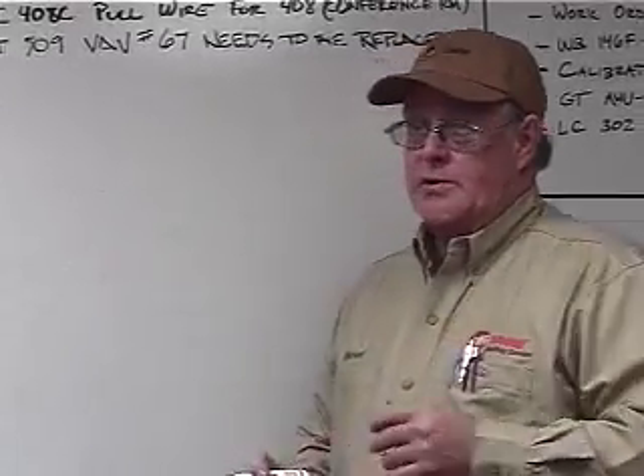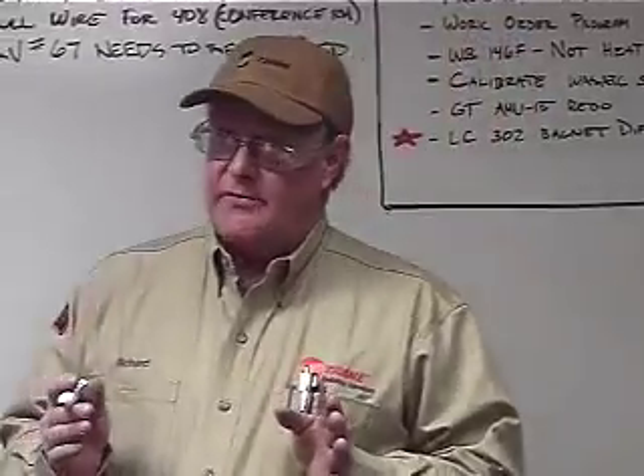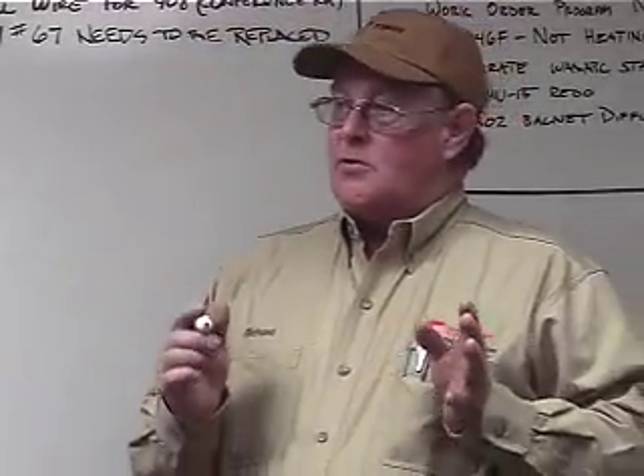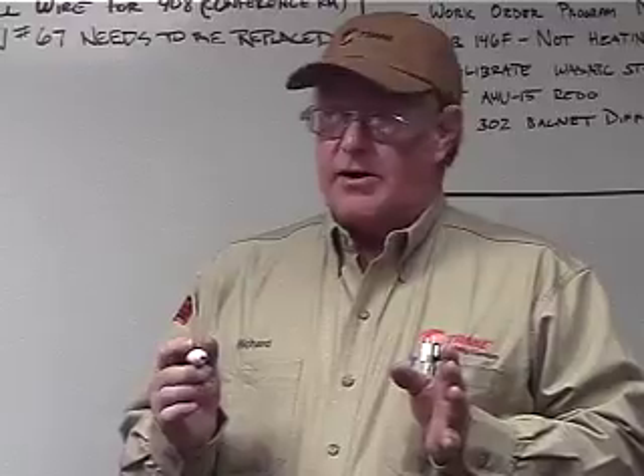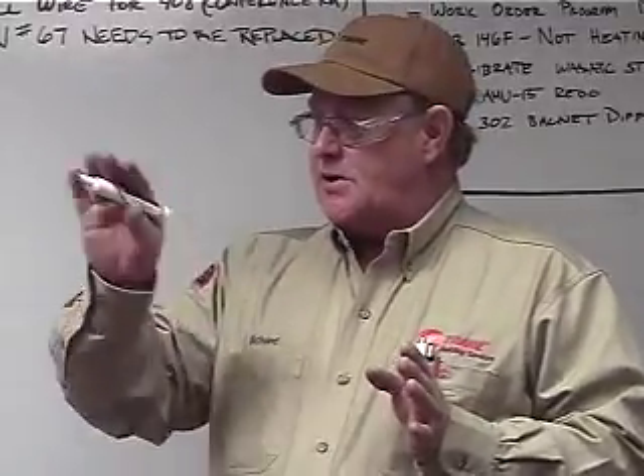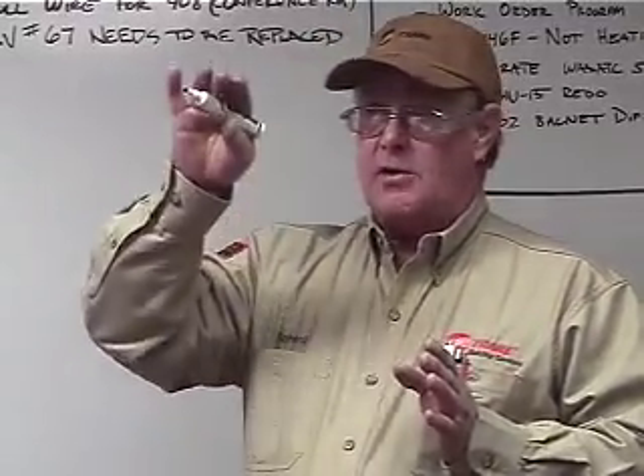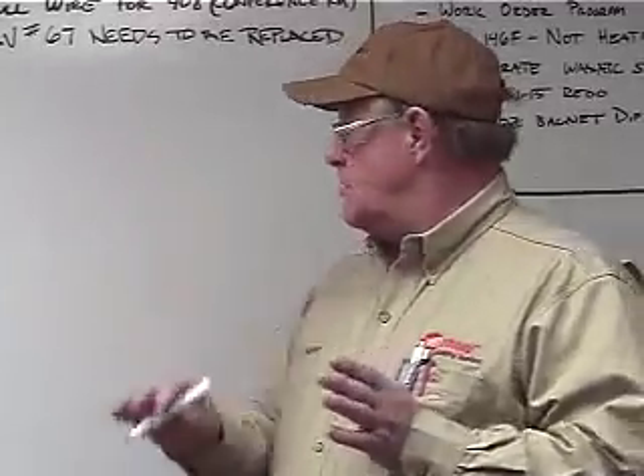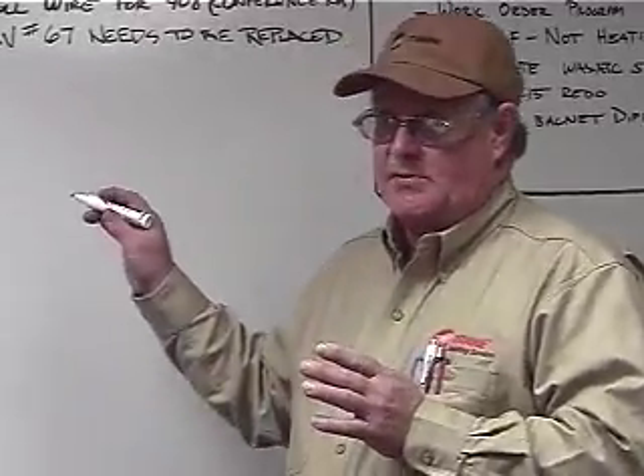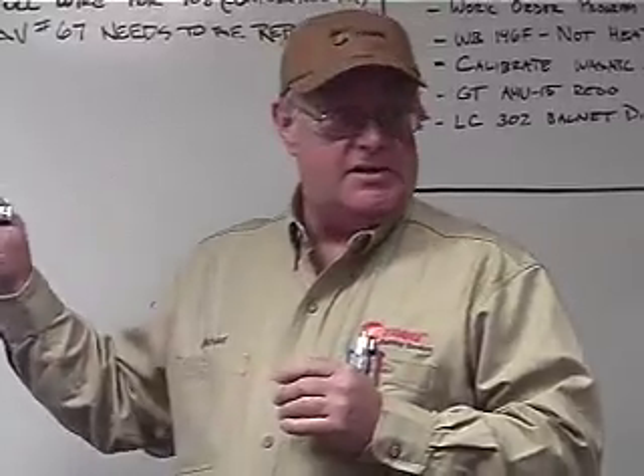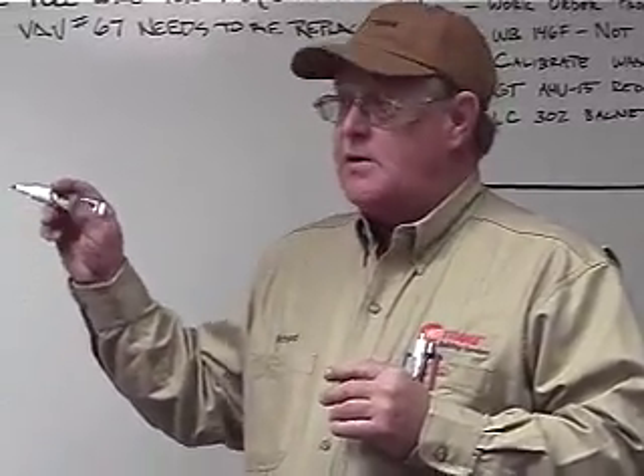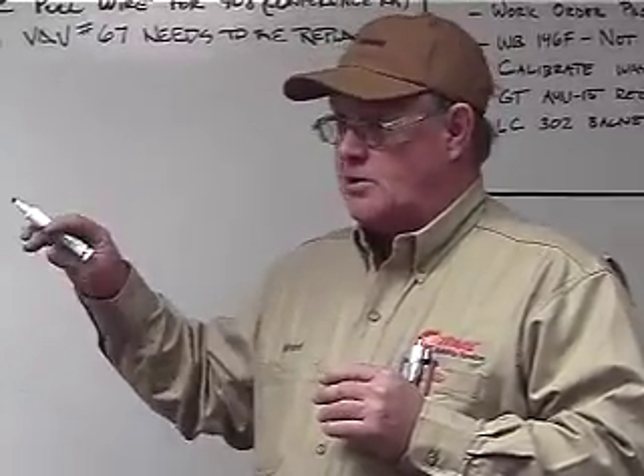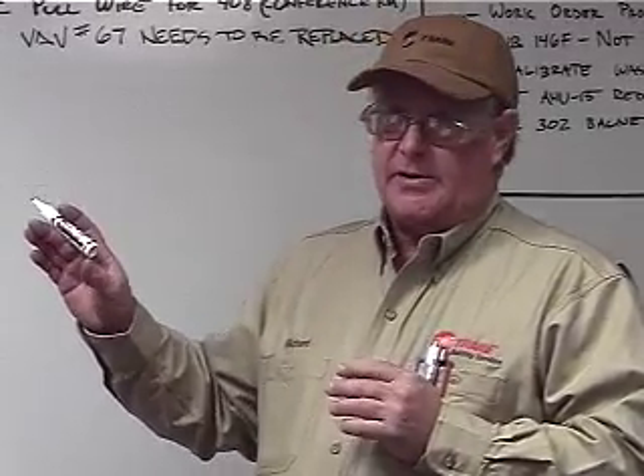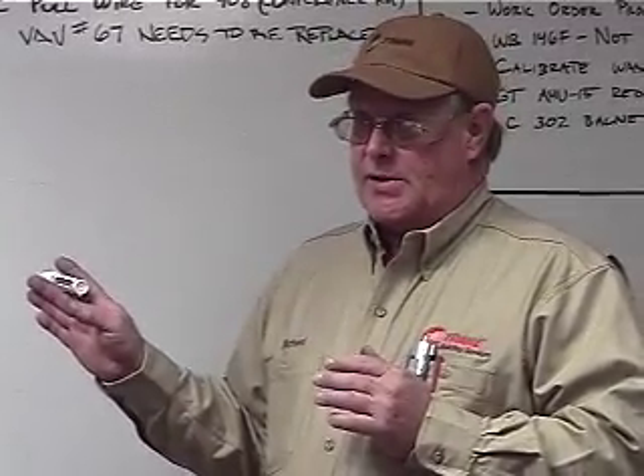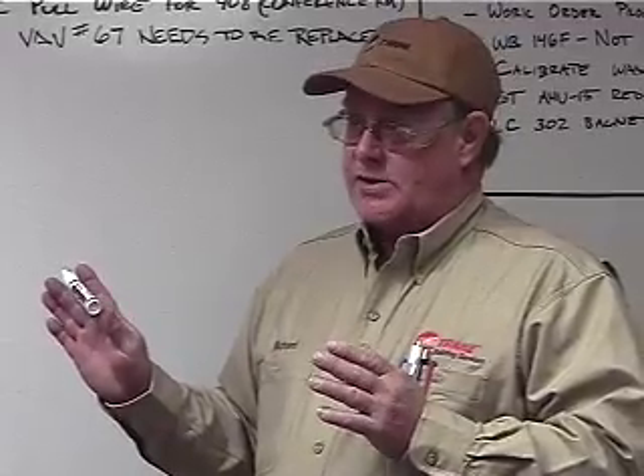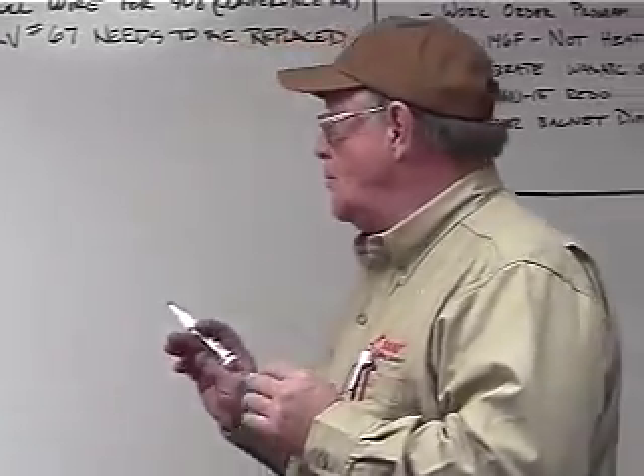First stage impellers or your first stage vanes, we have two stages of vanes. One's your first stage, which is right there by your suction elbow. And you'll see an actuator, you'll see a long arm on there that opens and closes that set of vanes that I was talking about. But on your second stage, there's another set of vanes in there that will actually open and close simultaneously with your first stage. And that's what your actual capacity control is on it.